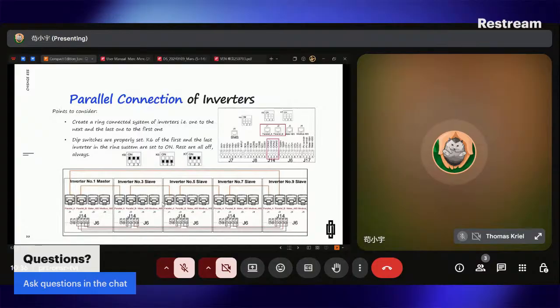And now let's talk about the parallel connection of the inverters. It's pretty simple. We need to make sure the wiring is correct. It's two parts. We need to connect the J14 terminals. First, we need to connect the master inverter's pin 3 and 4 to the slave 1's pin 1 and 2, and the second, this is the first slave machine, so we need to connect this one's pin 3 and 4 to the next one's 1 and 2. So 3 and 4 connect to the next one's 1 and 2. Then the last slave inverter's 3 and 4 connect to the master inverter's 1 and 2. So it will be a circle. So that's the first part.